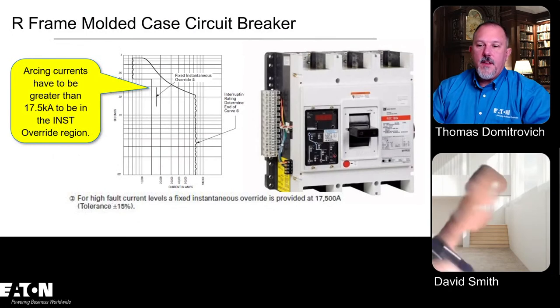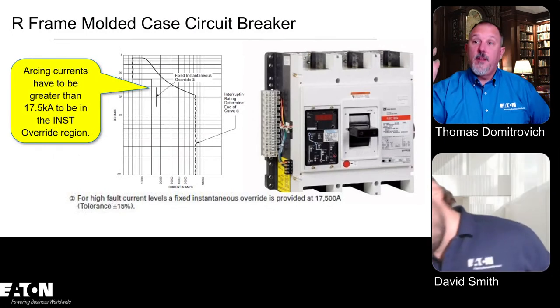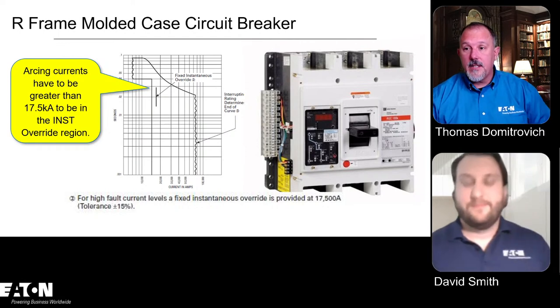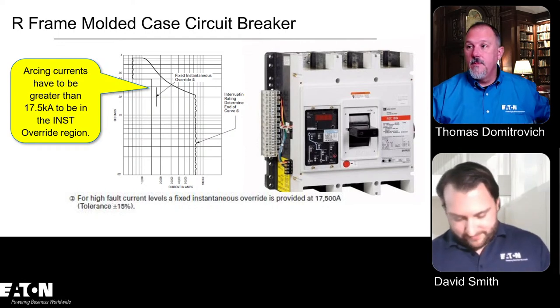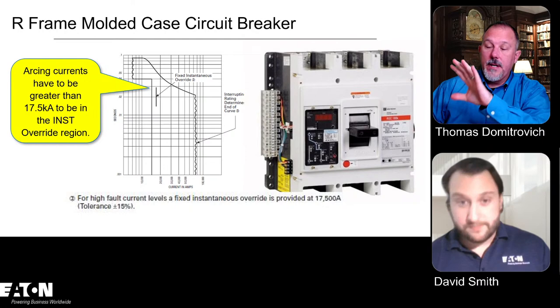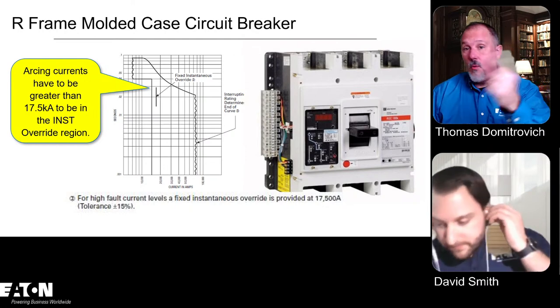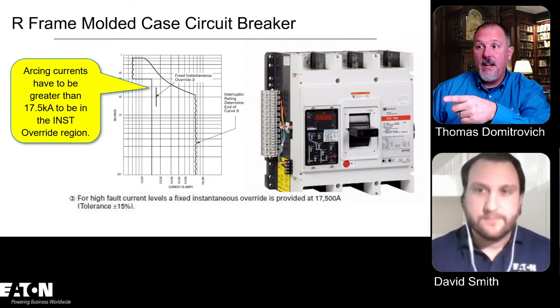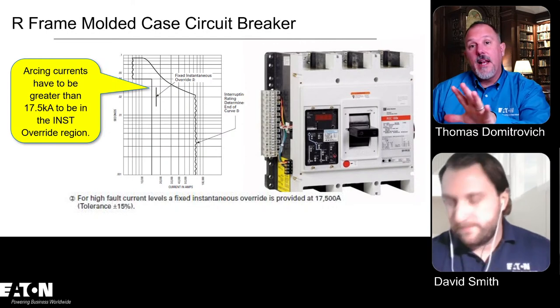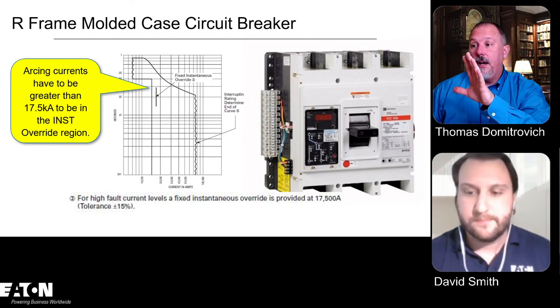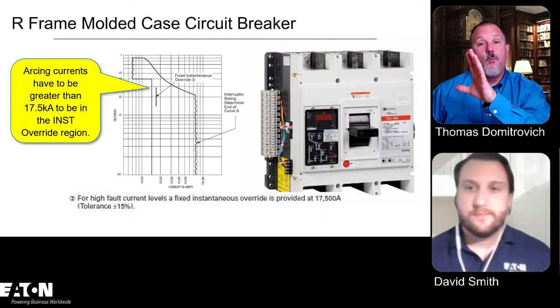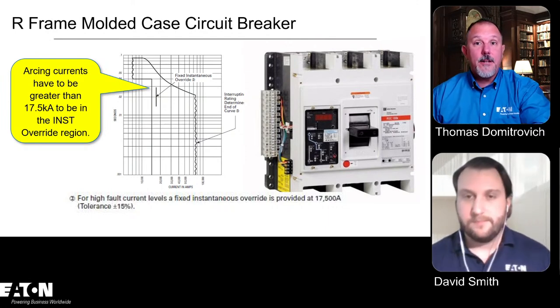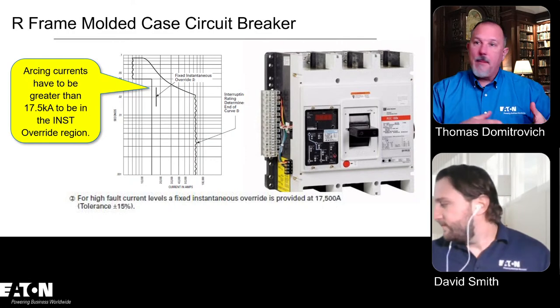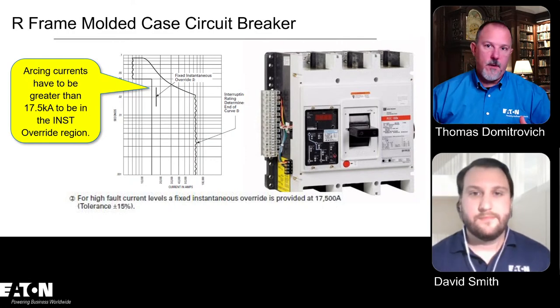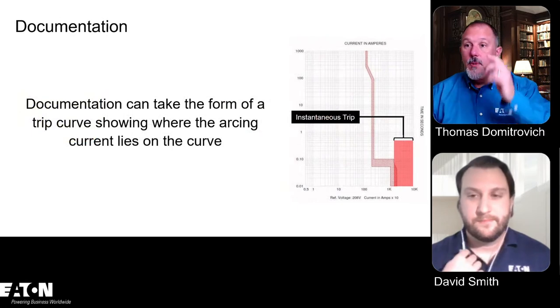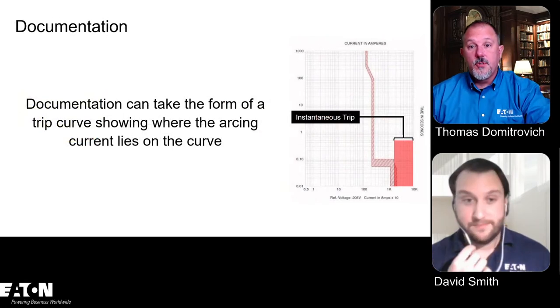So if you think about these, seriously, use him and abuse him, email him, ask him questions. He's good at that stuff. So this is your instantaneous on an R-frame circuit breaker, way up there, 17,500 amps. And think about it. If you are using this circuit breaker and adjusting it down to like 800 amps on an 800 amp application, that instantaneous is way over to the right, and you will be in the long time region from an arcing current perspective.